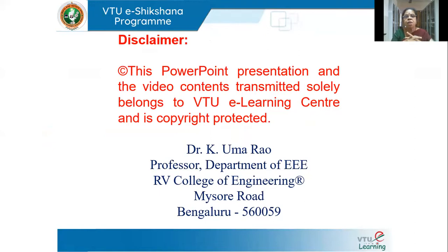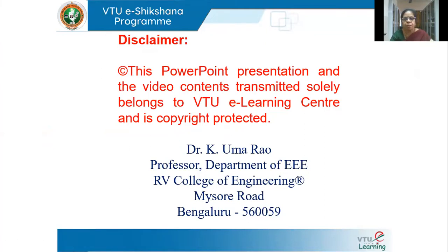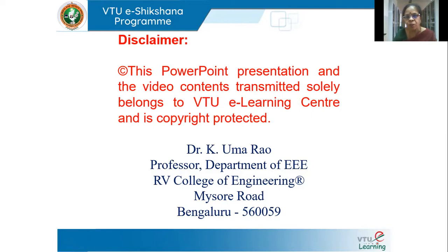We have seen in string insulators that the voltage is not uniformly divided. Even though the disks are identical, because of the shunt capacitance, we get unequal voltage distribution, with the voltage being the least in the disk close to the cross-arm and the voltage being maximum in the disk closest to the conductor. This reduces the string efficiency.